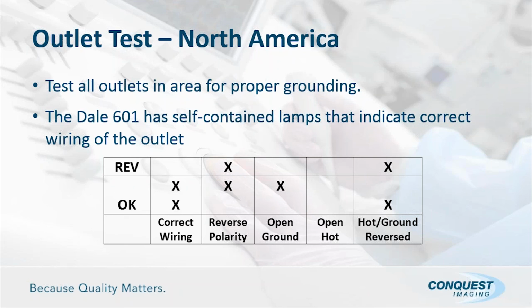So there is one condition that we'll talk about again, but I want to point out that no meter really has the ability to indicate when the ground and the neutral are reversed, because they all go back to the earth ground eventually, which is neutral. And so they can't give you that indication. And we'll talk about this again in just a little while.